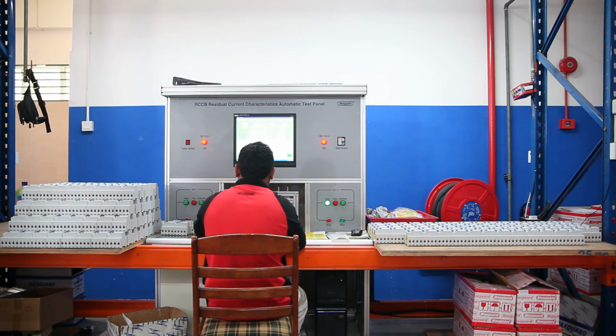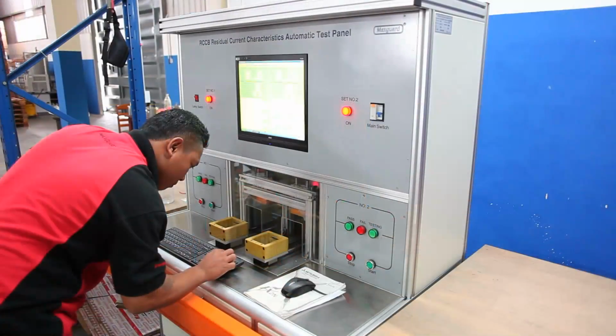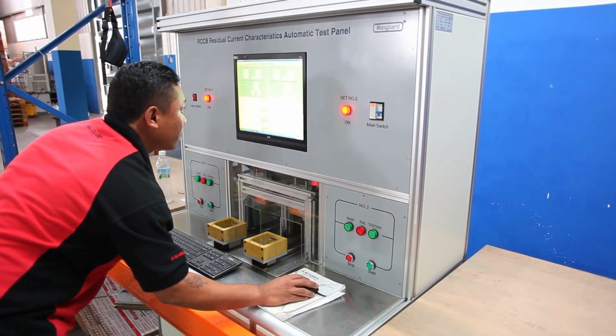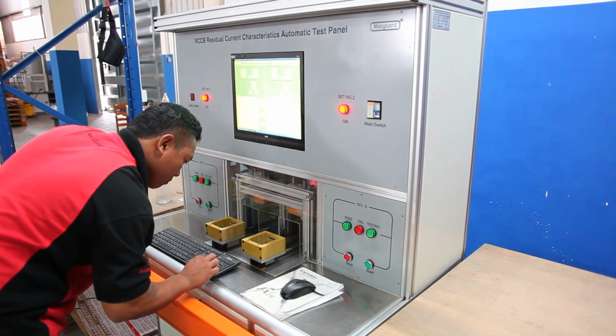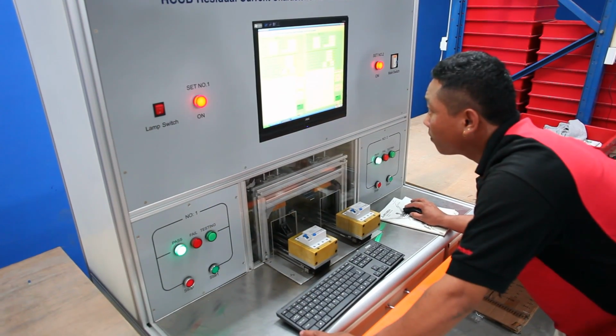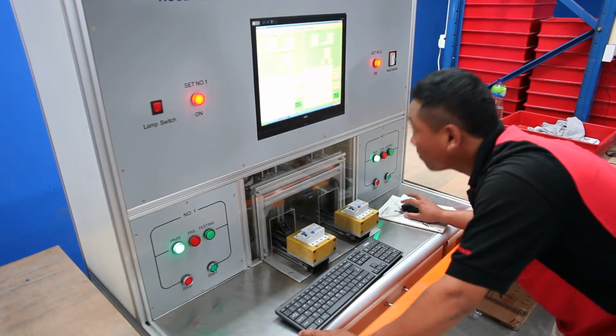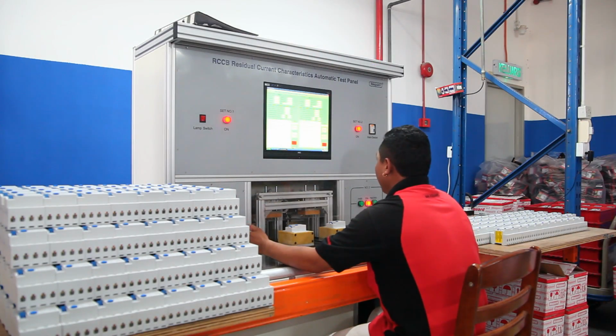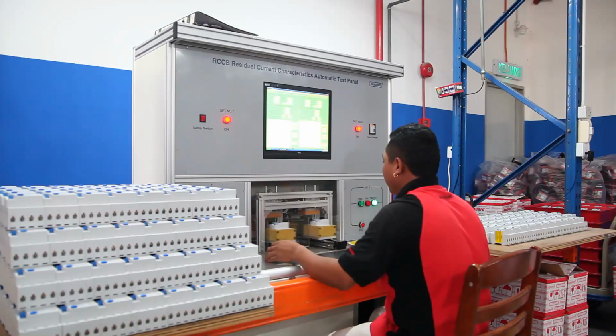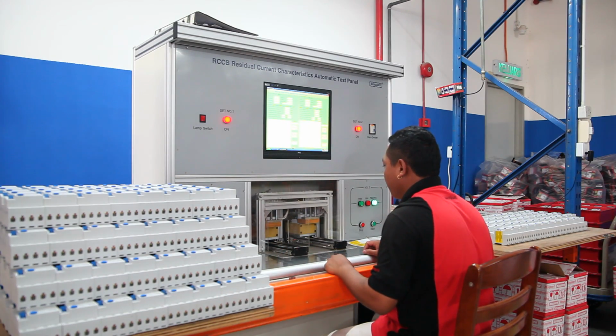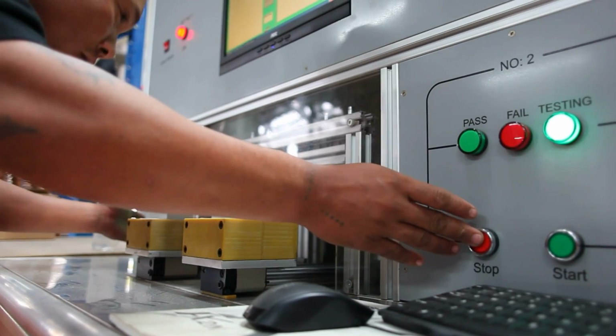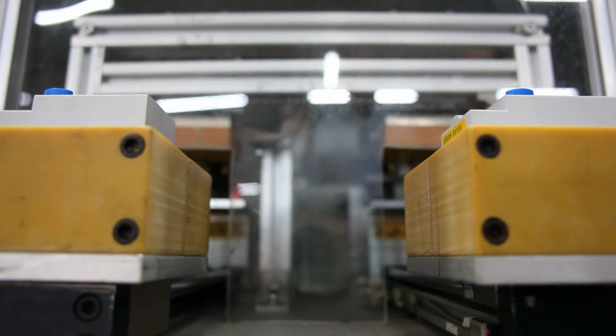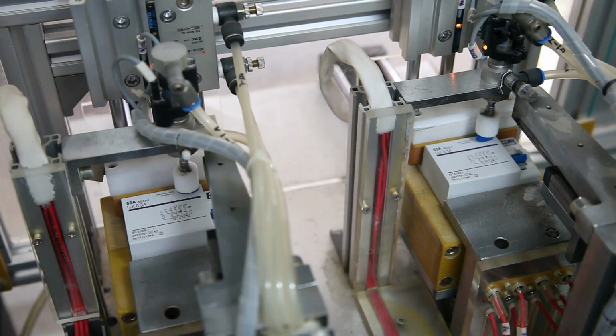In-house residual current-operated circuit breakers tester. The RCCBs are automatically tested for tripping characteristics using the external test button and also simulation of an external preset leakage fault current to activate tripping. The tripping time, which is also a crucial element, must be verified to check compliance. Trip-free is also verified and tripping time registered. All settings are preset according to rated markings of the RCCB. Tripping time is less than 0.1 second.